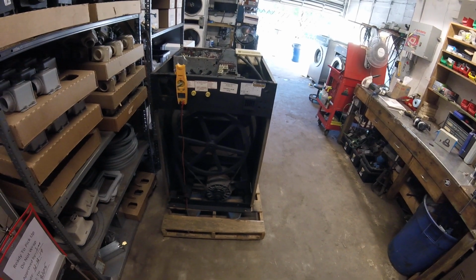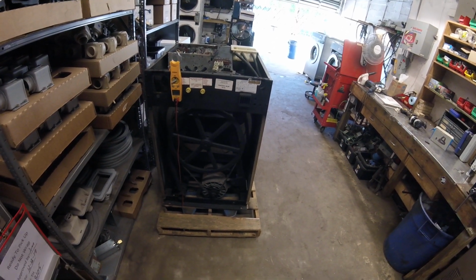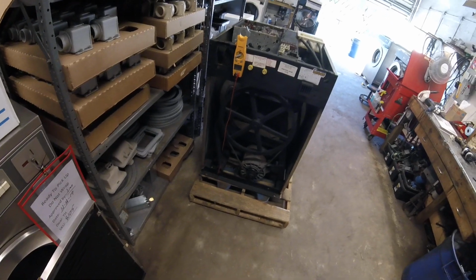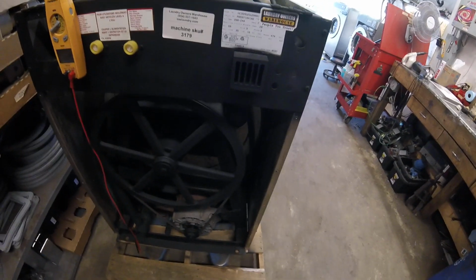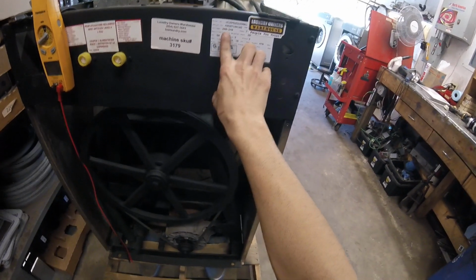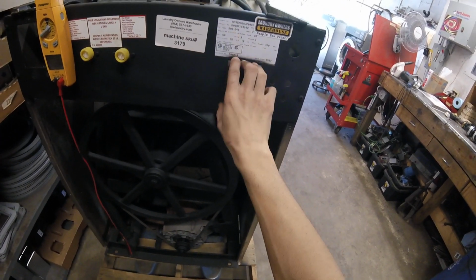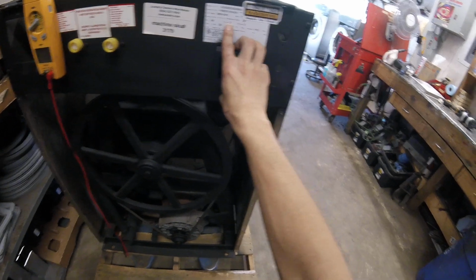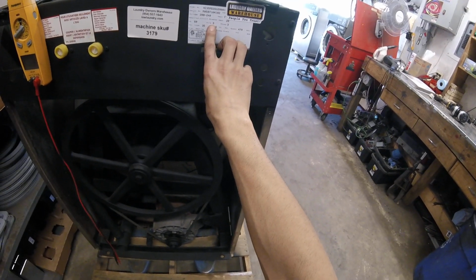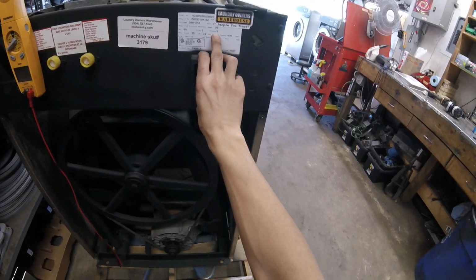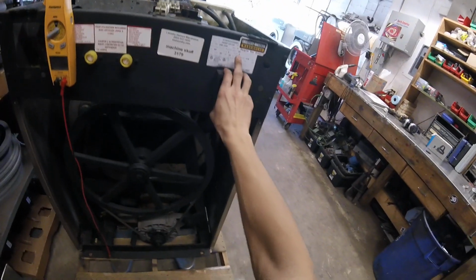Verifying voltage and power hookups on a commercial washing machine. All you need is a voltmeter. Any voltmeter will do, it doesn't have to be fancy. You're going to want to check the label on the back of your washing machine, see what voltage the manufacturer says you should be getting, how many wires. This is the hot wires, there will be one additional ground wire, and if it's single or three-phase. Now this one's three-phase at 208 to 240.